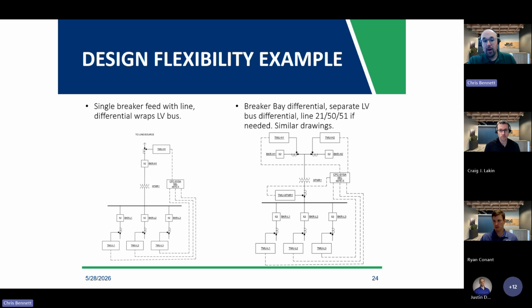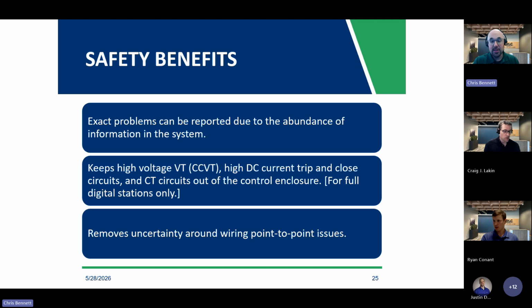On the right, we can expand that idea with minimal increase in the design sheets, if you want to call it that. If we wish to expand it to a breaker and a half bay, a ring bus bay, and add an additional zone of protection around the transformer, here I have it protecting the bay as well as the transformer. You can also customize it to be just the upper bay as a bus differential. And the transformer differential can be reconfigured to be the high side transformer CT down to the feeders. Almost all the drawings would be exactly the same here. The biggest lift here would be more of the programming and the general arrangement of your software. So definitely some heavy design benefits there, reducing the amount of time and the amount of resources needed for customization.